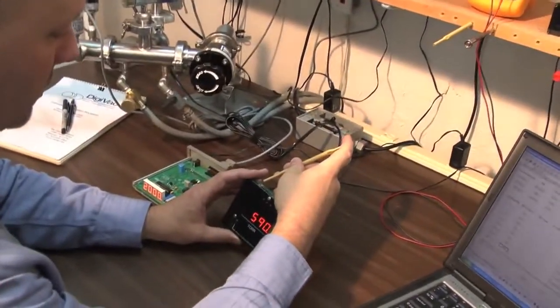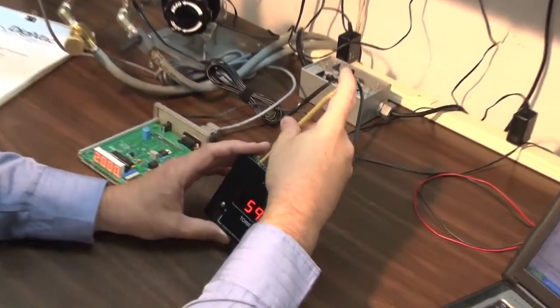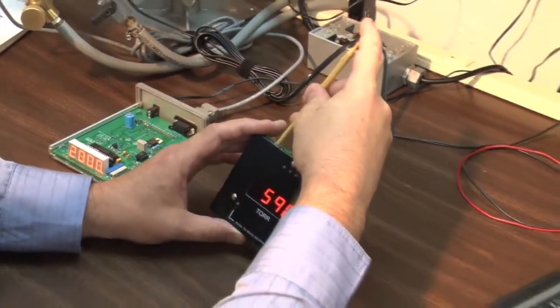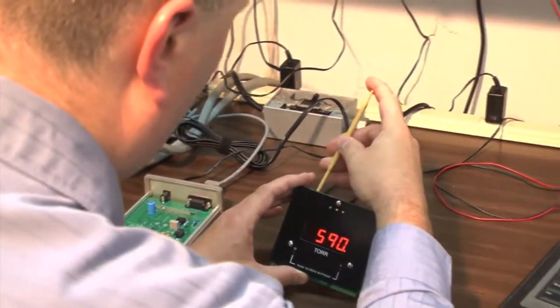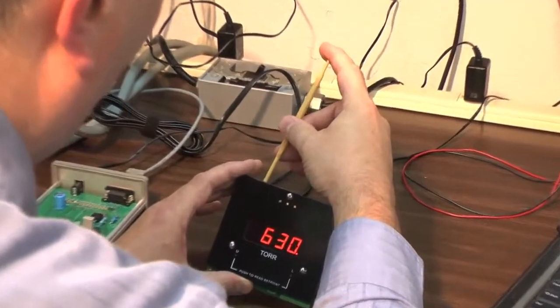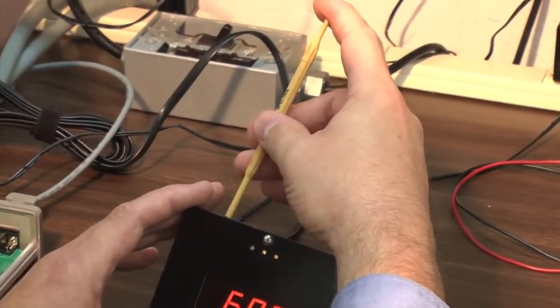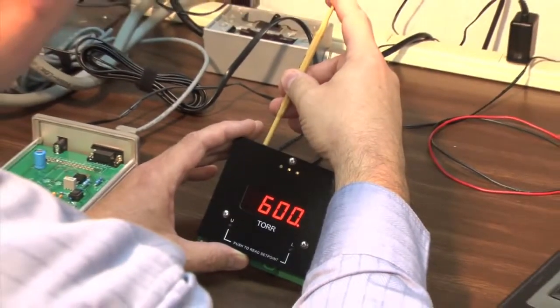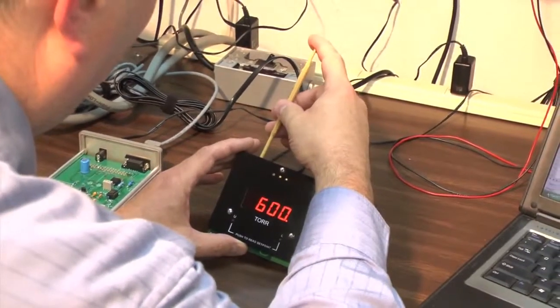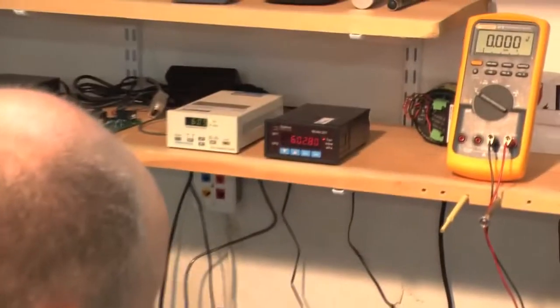Using the span adjustment on our 801W, we're going to increase the potentiometer clockwise so our 801W reads right on the threshold of 600 torr. Baratron reads 602. 801W reads 600. That's a good start.